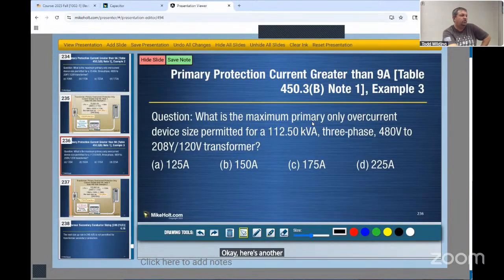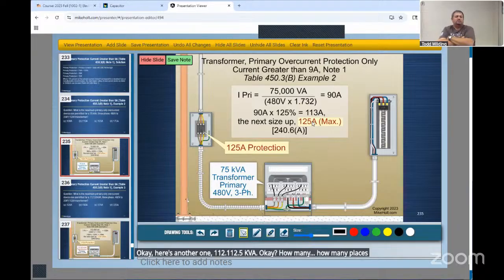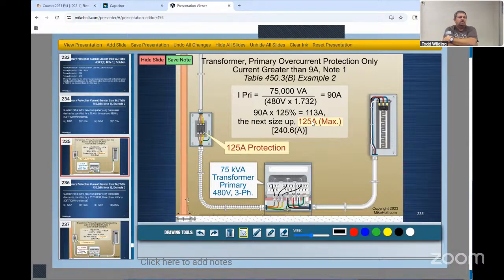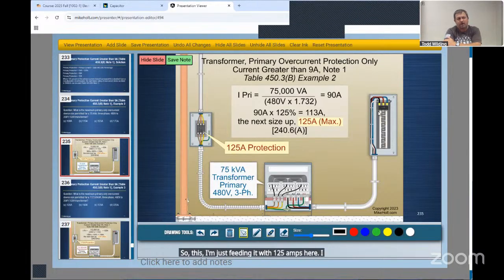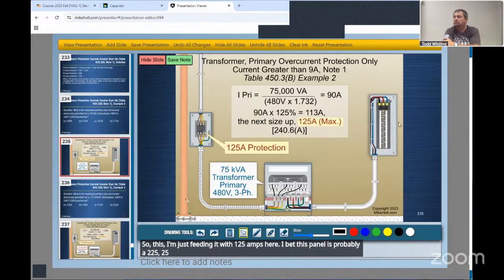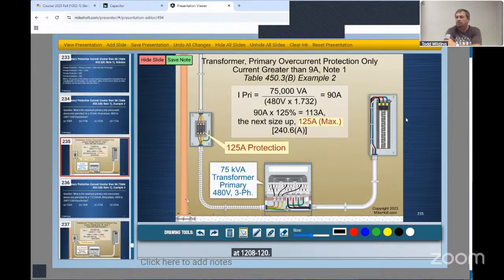Okay, here's another one, 112.5 kVA. How many places would you see this? This one right here is going to be real common. How many amps do I have on the secondary there? I bet I'm close to 200, or actually more than 200. I'm just feeding it with 125 amps here. I bet this panel is probably a 225, 250 amp panel at 208/120, which would be common. You'll see that in a lot of buildings.